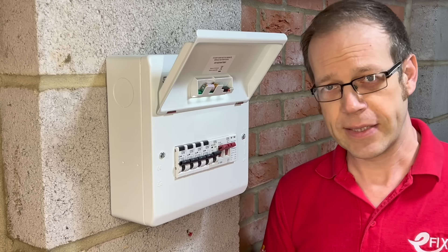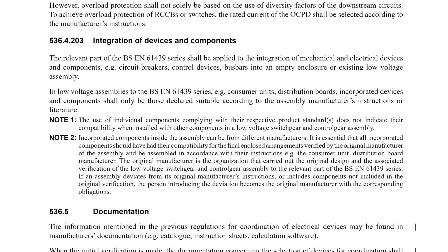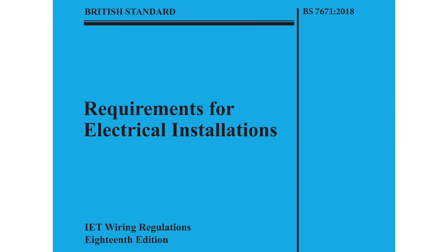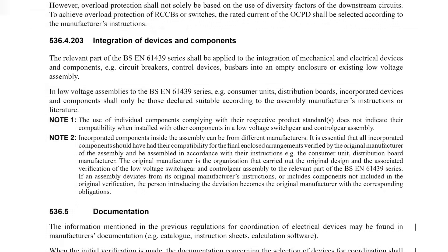The regulation that relates to all this is 536.4.203, and this isn't brand new — it's been around since the original 18th edition in 2018. It reads: the relevant part of the BS EN 61439 series shall be applied to the integration of mechanical and electrical devices and components — e.g. circuit breakers, control devices, busbars — into an empty enclosure or existing low voltage assembly.